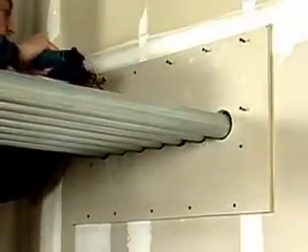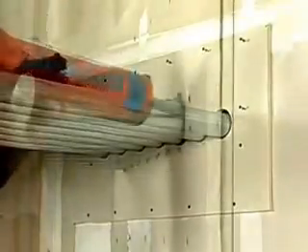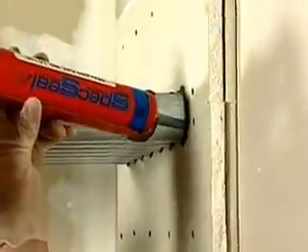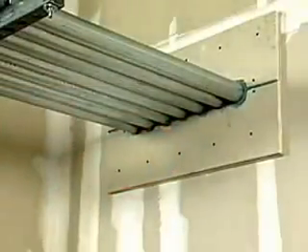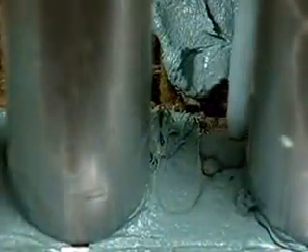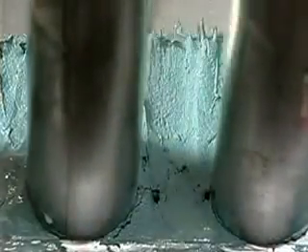While all openings must be sealed within the requirements of a given UL system, excessive annular spaces and grouped penetrations present an especially difficult problem because there are so few UL systems available for these conditions. When a UL system is not available, contact the Firestop manufacturer's technical service department for instruction prior to installation. The instructions will not only indicate how to restore the fire rating, but also how to deal with the multiple penetrants, the large opening size, and any other variables that need to be addressed.